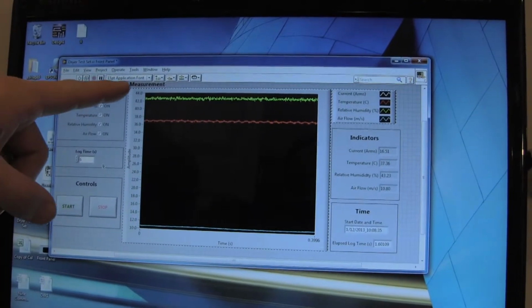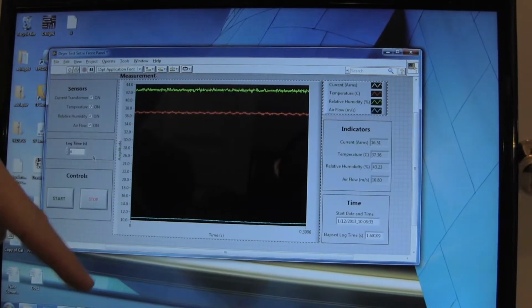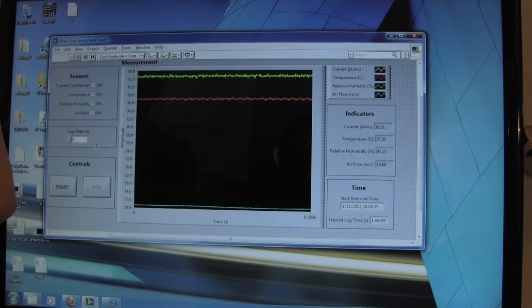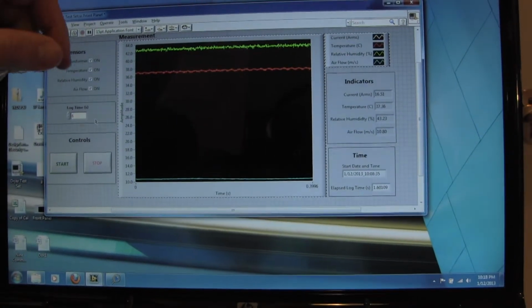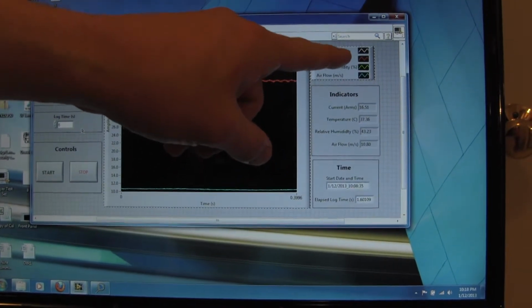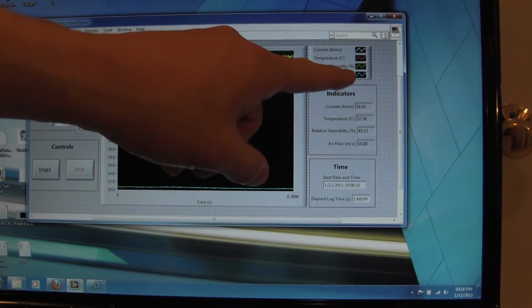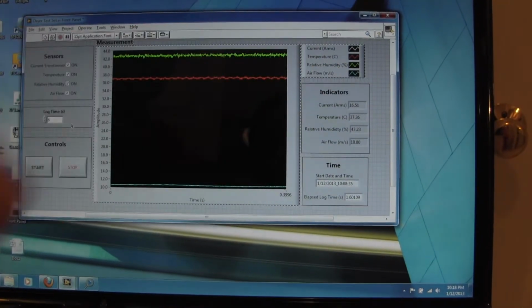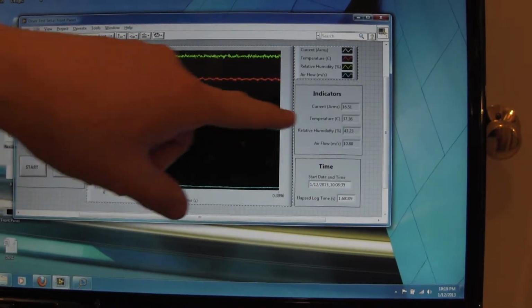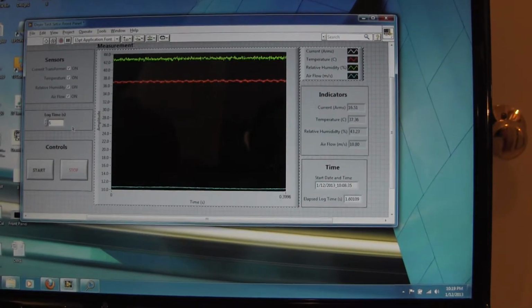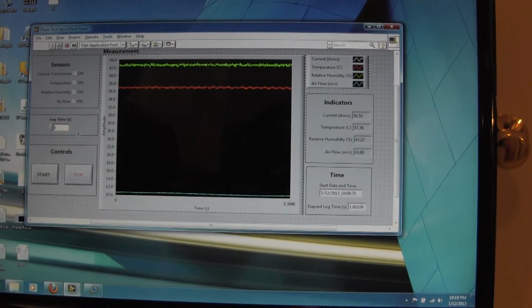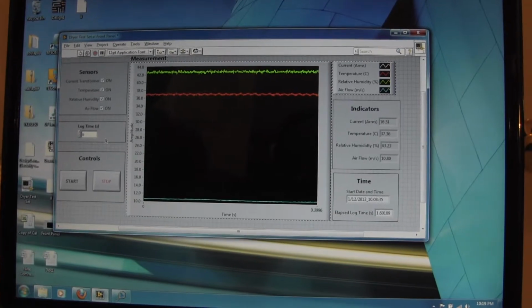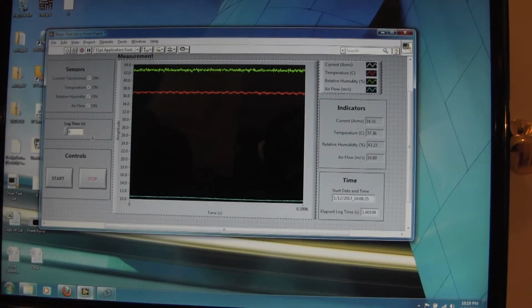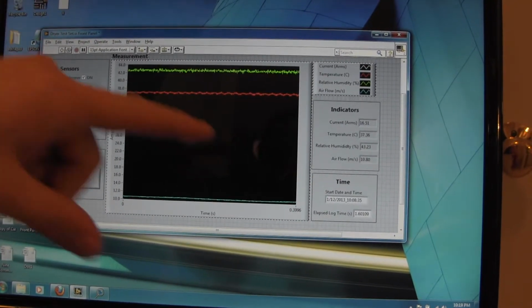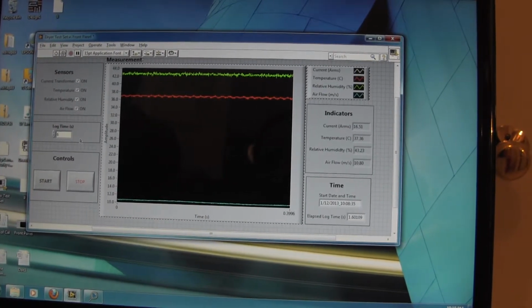This graph labeled measurements is a graphical representation of all 4 of your sensors in real time. Here's a legend right here: white is for current, red is for temperature, green is for relative humidity, and airflow is blue. Here you have your indicators, which are just a numerical representation of your 4 sensors. So you can look at the graph, they're being graphed in real time. You can also look at your indicators, because they're being populated in real time with the numeric values. Then what you have here is a start time and date.